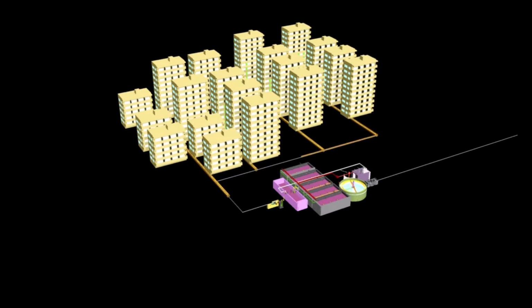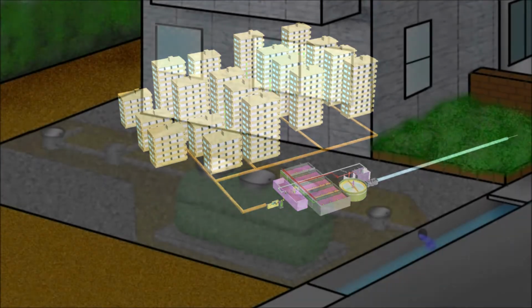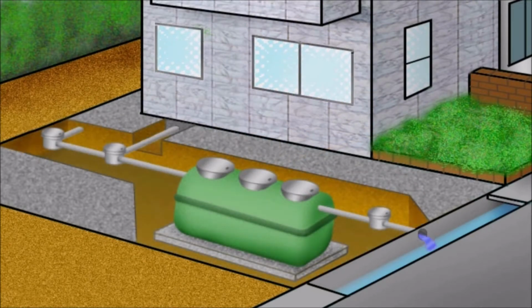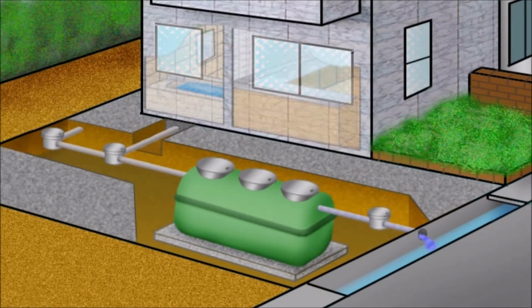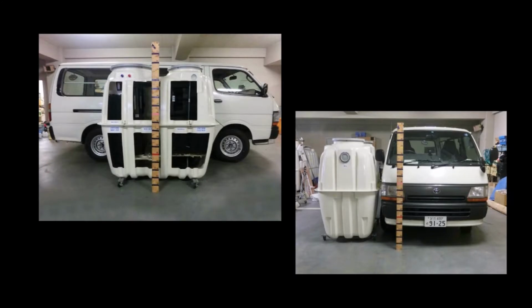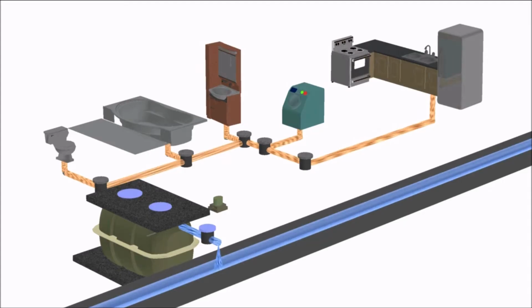Depending on the amount of wastewater received, there are large-scale JOHKASOU which work as wastewater treatment plants and small-scale JOHKASOU installed in houses. The smallest JOHKASOU is designed for 5 persons or 5 PE. JOHKASOU treats wastewater from flush toilets together with gray water, which includes wastewater from the kitchen or washing machine. To ease understanding, it is called gappei shori JOHKASOU.